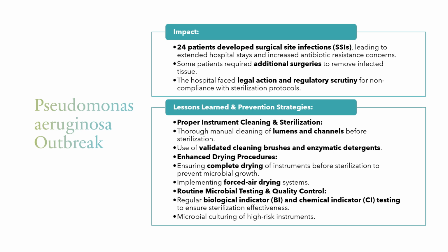So some lessons learned and prevention strategies. Proper instrument cleaning and sterilization. The staff was educated on how to properly flush those lumens and instrument channels. They also were shown how to use cleaning brushes and enzymatic detergents, as well as enhanced drying procedures.